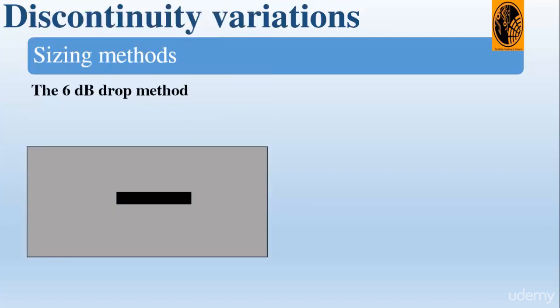Let's see the 6 dB drop method. This method is used for sizing large reflectors. If the probe is moved until the signal amplitude from a reflector drops to half its original screen height, it can be said that the sound beam is half on and half off the reflector. By moving the probe until the signal from the end of the large reflector halves in height, we can estimate that the edge of the reflector is immediately below the center of the probe. This is called the 6 dB drop sizing method because the amplitude drops by half, which corresponds to 6 dB, when the probe is moved to the edge of the large reflector.